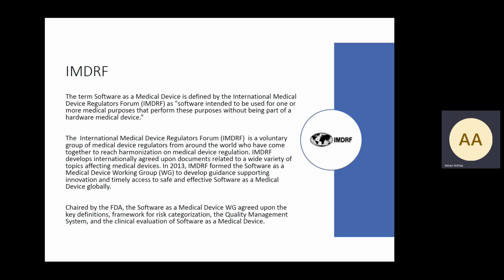And there are 4 documents mentioned at the bottom point, and the IMDRF is chaired by the FDA. The 4 documents are titled Key Definitions, framework for risk categorization, the quality management system, and clinical evaluation of software as a medical device.